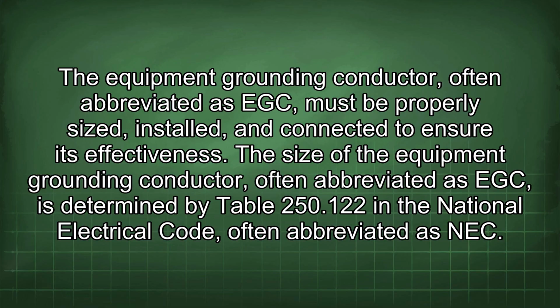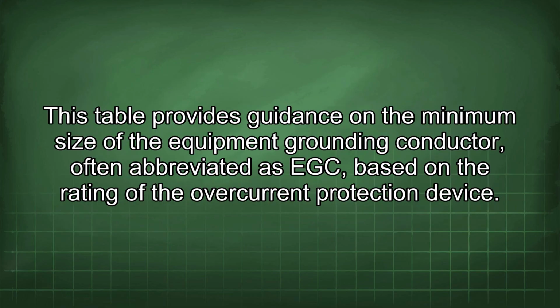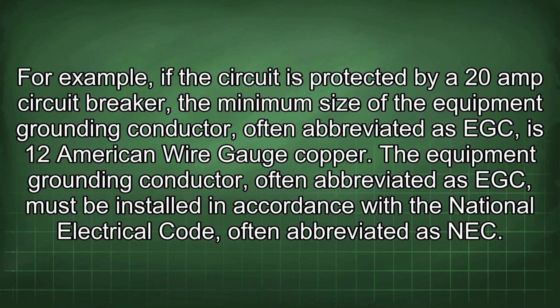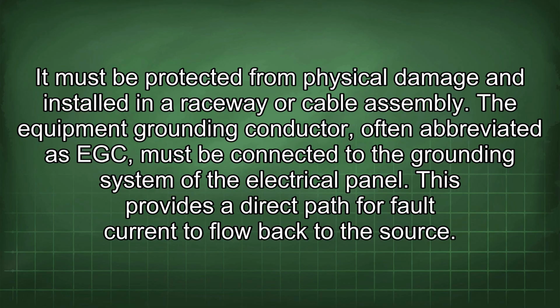The size of the EGC is determined by Table 250.122 in the NEC. This table provides guidance on the minimum size of the EGC based on the rating of the overcurrent protection device. For example, if the circuit is protected by a 20 amp circuit breaker, the minimum size of the EGC is 12 American wire gauge copper. The EGC must be installed in accordance with the NEC. It must be protected from physical damage and installed in a raceway or cable assembly. It must be connected to the grounding system of the electrical panel. This provides a direct path for fault current to flow back to the source.